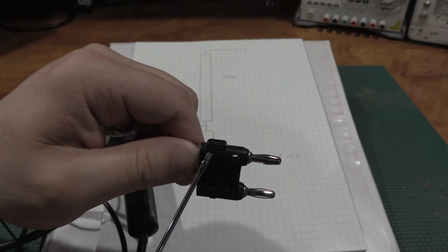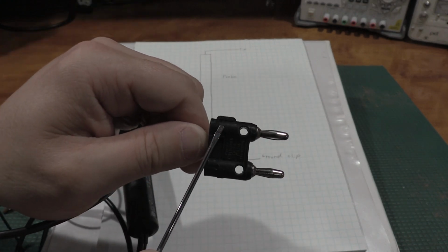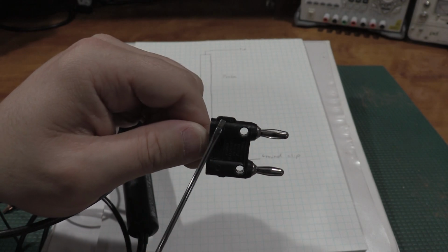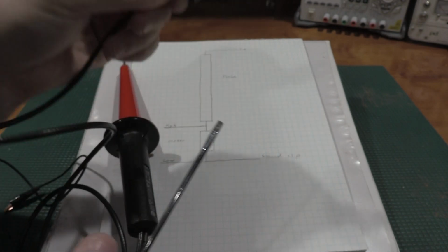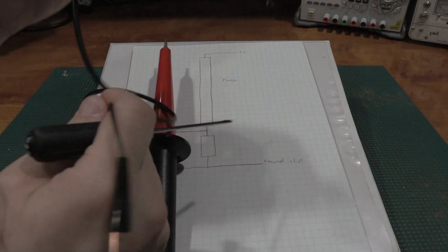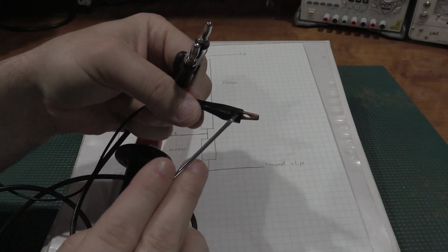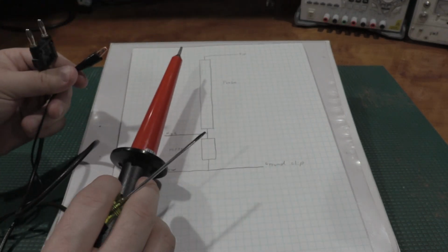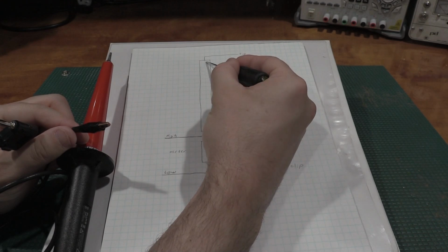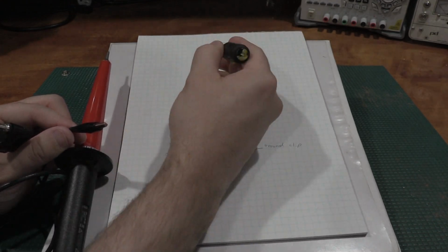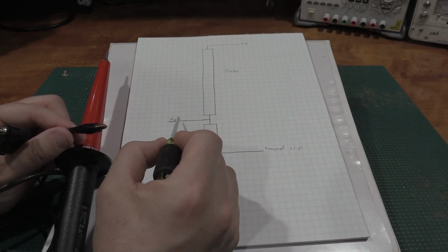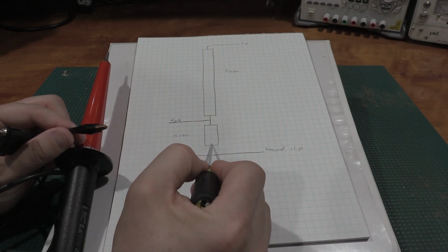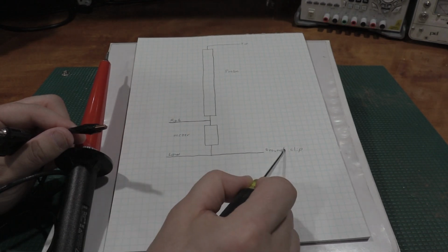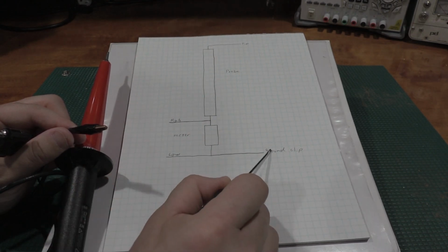Let's see if I can get the camera to focus on that. There's a GND on that tab. That always has to go to the low side of the meter because that is hooked to the ground clip of the probe. So you have the division resistor. Meter taps off at the bottom of the division resistor. We have the meter's input impedance, and then we have the low side of the meter and the ground clip.